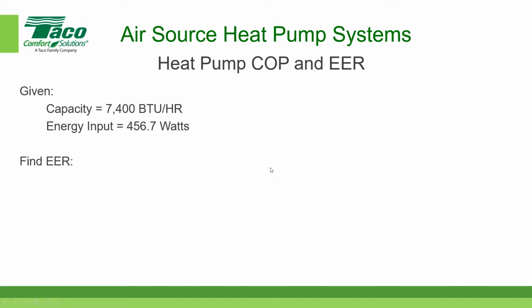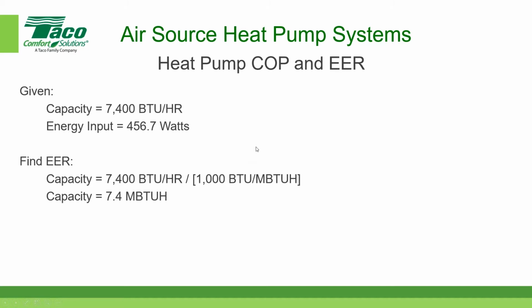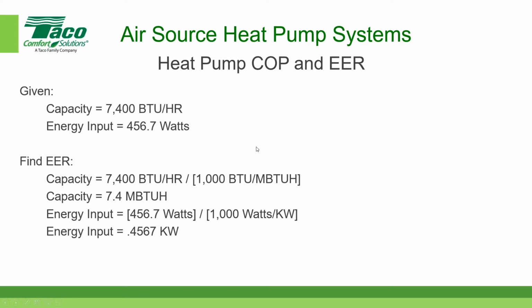456.7 watts. The EER is equal to, we'll take the BTUs per hour divided by 1,000 BTUs for MBH. That's 7.4 MBH, and the energy input, we can convert that into kW, 0.4567 kW. So 7.4 divided by 0.4567 kW is equal to 16.2.